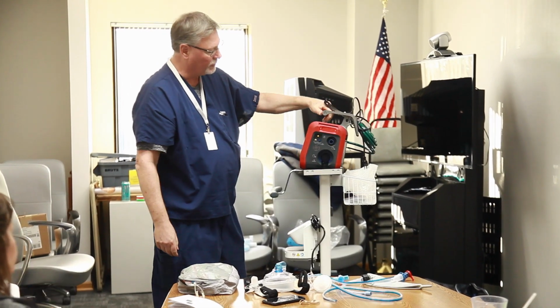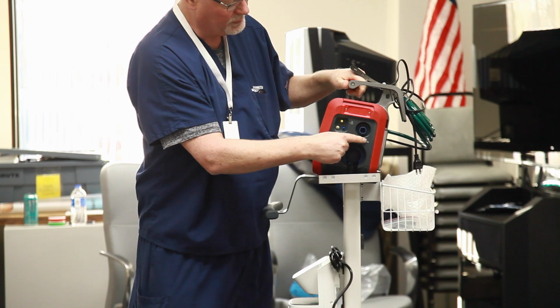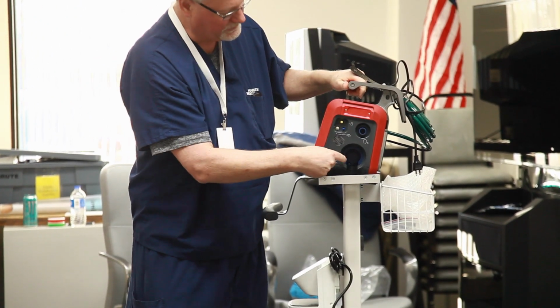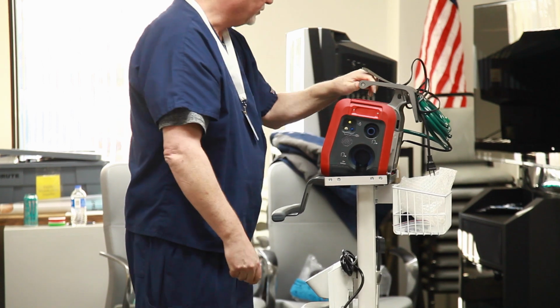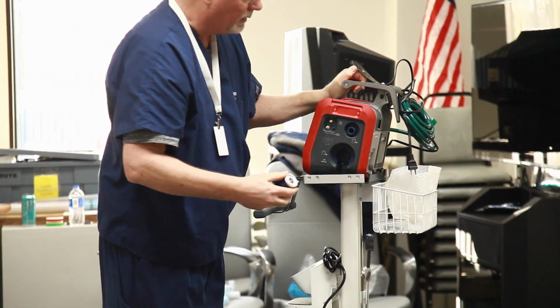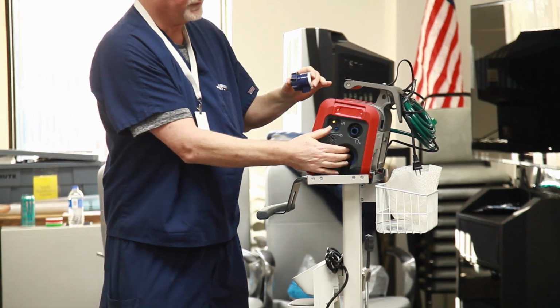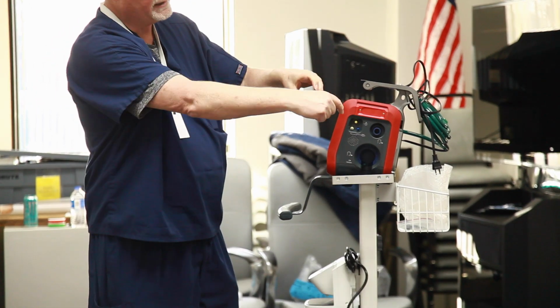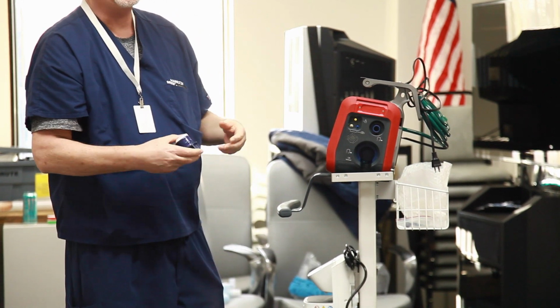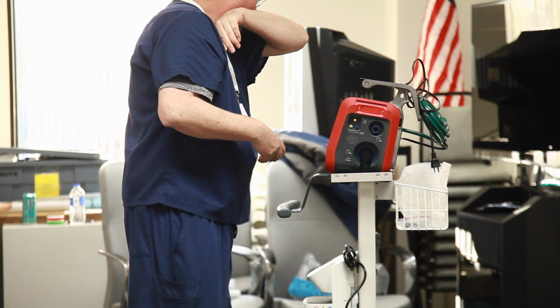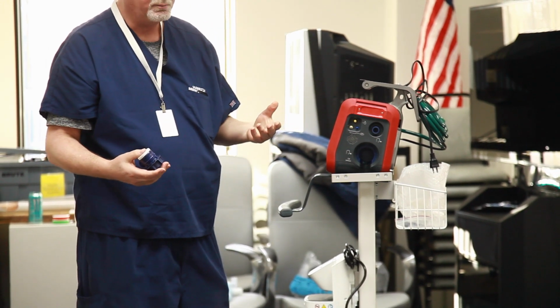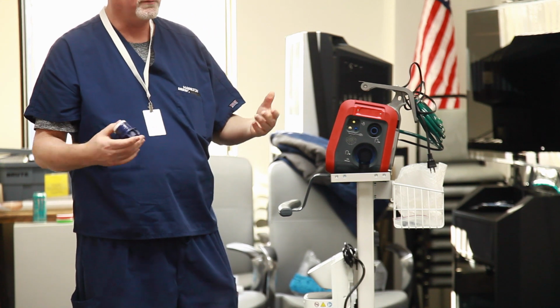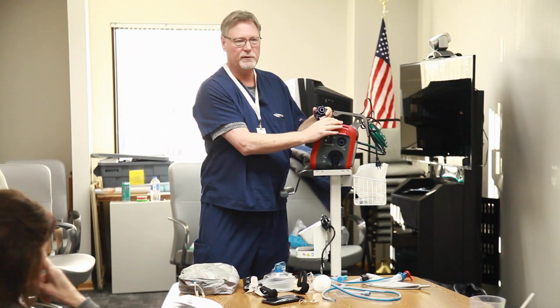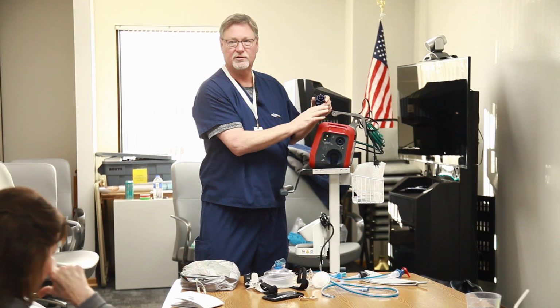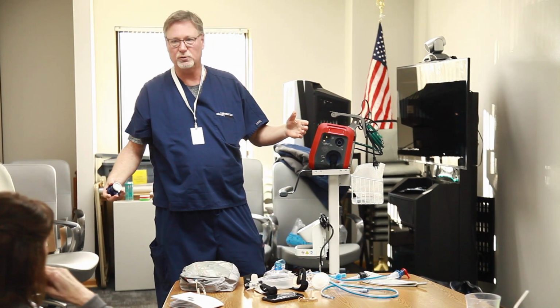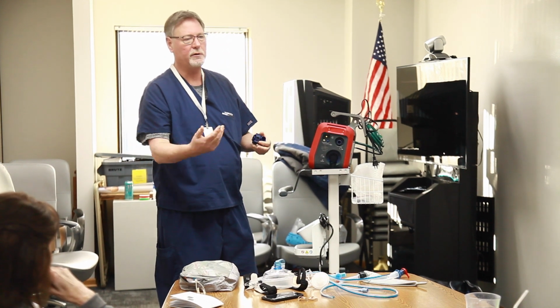Sneaking around to this side is where everything is going to get hooked up. We have pictures here to the patient. So this is the inspiratory side. From the patient, this is the expiratory side. You'll notice that the expiratory valve is going to go in there. Nothing goes inside this ventilator. So air is just going to go inside the valve and go right out the bottom. That means if you have a COVID patient or something crazy, they were coughing, spewing all over the place, you don't have to do anything special with this because nothing touches the inside of the ventilator. Just wipe it down. Everything is going to be single patient use. Everything comes off, wipe it down, and you can put a new circuit back on.